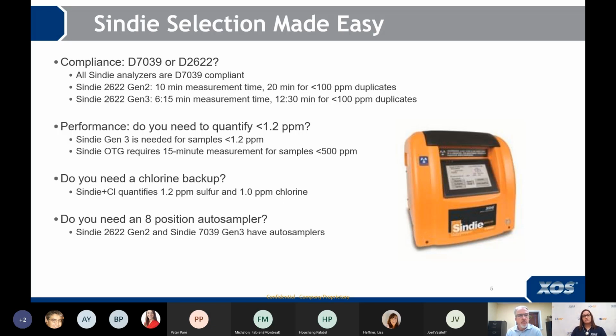And if you do need the 2622 compliance, another thing you might want to think about is measurement time. Because if you've read the method, you'll know that duplicates are required for samples 100 ppm and less. So this means when you factor in the background time and the duplicate measurement on our generation 2 2622, that can be 20 minutes to run a sample. Whereas if you consider the generation 3, due to the better quality of optics, we were able to reduce the background measurement time. So when you're running those 100 ppm and lower duplicates, instead of it taking 20 minutes, it only takes 12 and a half minutes. Okay, so that might be a consideration for you if you're running a lot of samples.